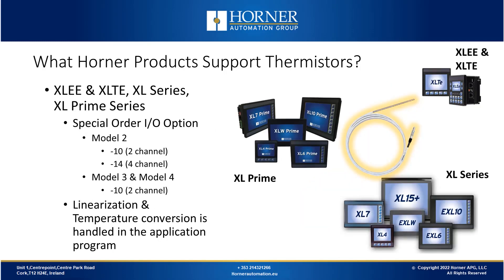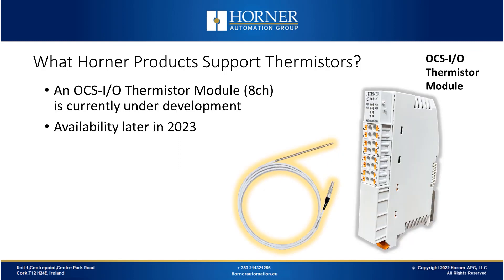You can find thermistor support as a special I/O option in the XLEE and XLTE — the XL series and XL prime series. The Model 2 I/O option is available with either a 2-channel or 4-channel special order option. Model 3 and Model 4, which have solid state outputs and slightly different mixes, have a 2-channel option for thermistor. Because this was added after the fact as a special order, the linearization and temperature conversion are handled in the application program. There is an 8-channel thermistor module currently under development coming for OCSIO later in 2023, which will also support linearization internally.